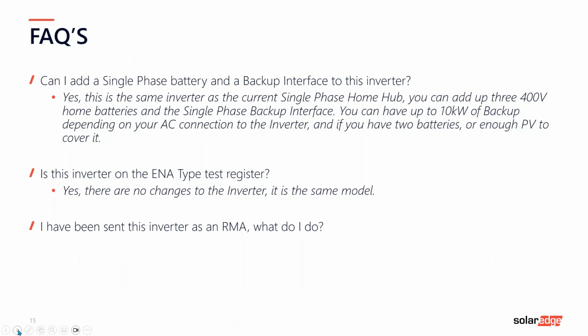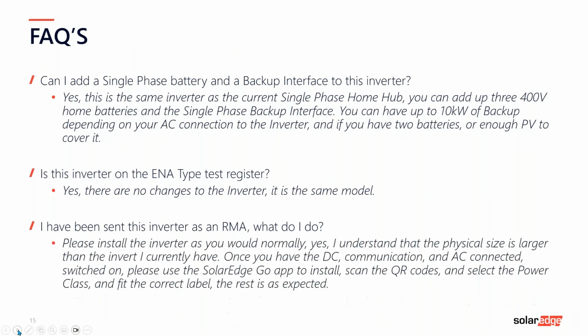The next one is: I've been sent this inverter as an RMA, what do I do? Please install the inverter as you would normally. There is a larger physical size to the 10 kilowatt than there is to the 3.68, but yes, you have now got an inverter that will do all of these power classes. So simply install the inverter, connect the DC, the communication, the AC, switch it on, use the SolarEdge Go app to install, scan the QR code, select the power class, and then fit the correct label. The rest is as expected, the rest is how you would normally do it.